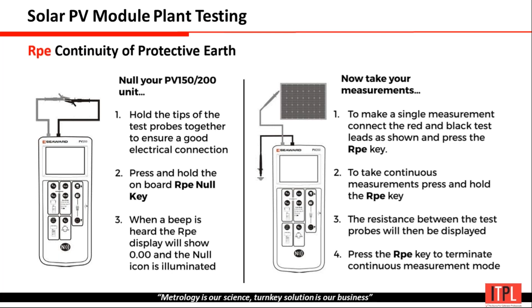This will ensure that your system, your solar panel or your string, is properly grounded. So this is the safety aspect parameter which we follow during the IV testing. This is the method you have to follow while doing the earth continuity testing. You just need to connect like this. One cable will connect to the structure of your solar panel, and the other one will connect to the earth pit, and with one press of a button, we get the earth continuity values on the instrument. After seeing the values, we can say that the continuity is perfectly okay, so our system is completely safe.